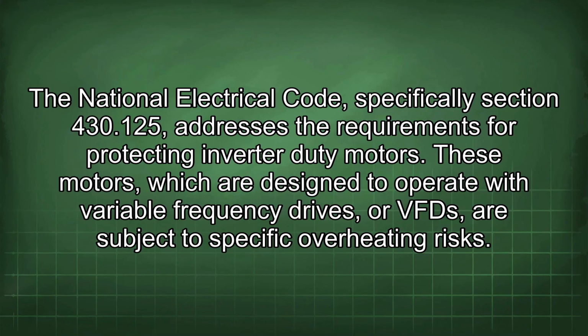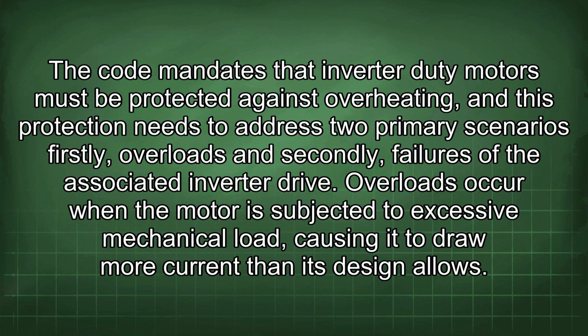The National Electrical Code, specifically Section 430.125, addresses the requirements for protecting inverter duty motors. These motors, which are designed to operate with variable frequency drives, or VFDs, are subject to specific overheating risks. The code mandates that inverter duty motors must be protected against overheating, and this protection needs to address two primary scenarios: firstly, overloads, and secondly, failures of the associated inverter drive.